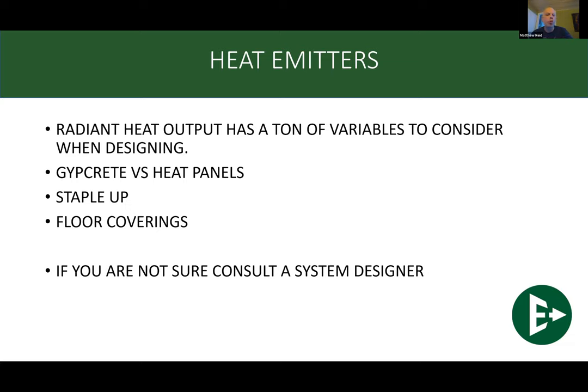What's your overpour going to be? Are you going to be using gypcrete? Are you using concrete? Is it going to be those heat panels, like I mentioned, that give you a much larger BTU per square foot output? Our friends at Uponor make them, Rehau make them, Heatlink have a couple. They can bump that BTU output into the 30s to give you more heat coming out of these heat emitters. Now, if it's just standard insulation with a gypcrete overpour, gypcrete has a different density than standard concrete, so that's going to create a different heat slab. These are things I'm going to want to know as a designer when I'm designing your system. You need to tell me so that I can get the piping sized right.